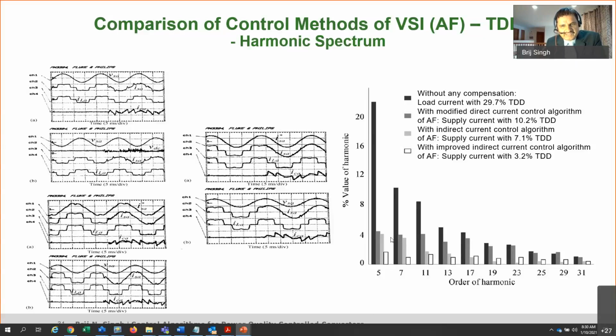My question is about the fifth harmonic you were explaining earlier. Without any compensation it's around 25% or so. With the first method, modified direct control, where you got 10.2% TDD, the fifth harmonic came down to around 5%. Then with the next color, 7.1% TDD, it's almost equivalent to 4%. And the fourth color, with the 3.2% TDD version, the fifth harmonic is much less.